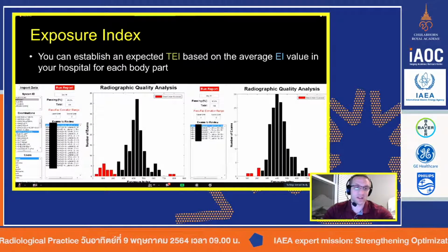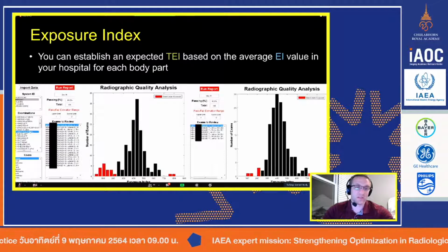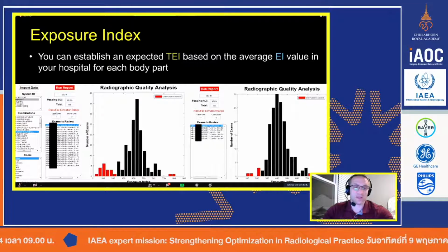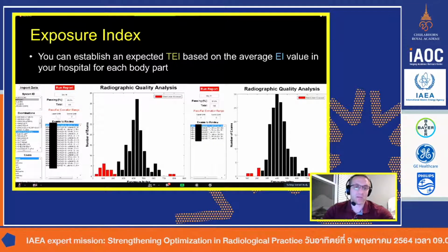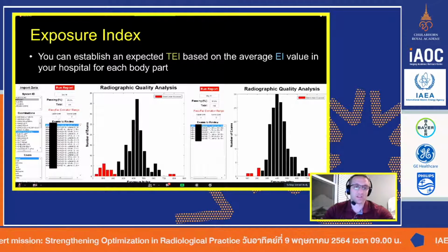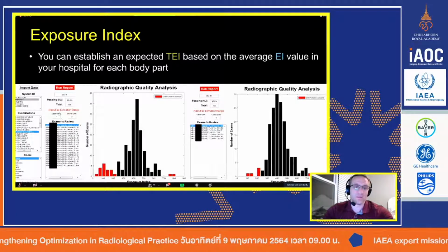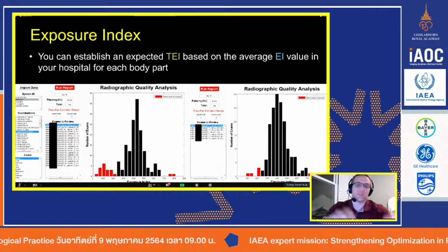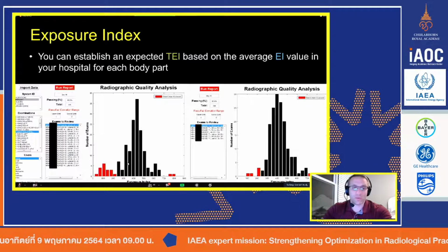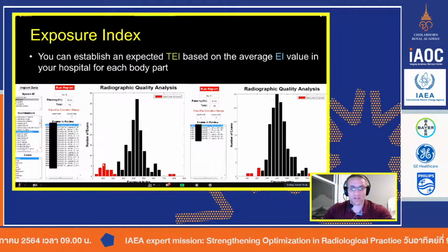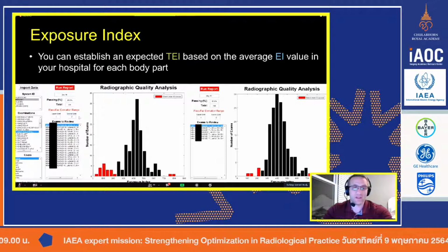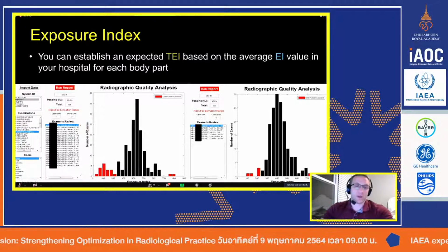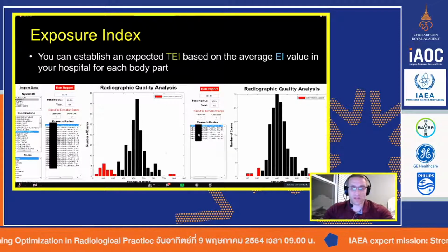So in this case, I have PA lateral, chest, PA lateral listed. And when I run this report, I can tell it my upper limit. I will pass or fail based on a deviation index of +1 and -2. That's just a random number. You could pick a completely different number if you wanted. And then any patient exam that falls outside of that range will be listed here. Now, this is just how I do my quality control. I've obviously blacked out the patient MRNs.